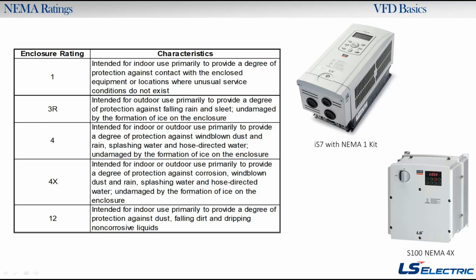Then there's NEMA 4 and NEMA 4X. Most people are usually requesting a NEMA 4X because a NEMA 4X can handle a hose being sprayed directly at it. We do have the S100 NEMA 4X, which is the second picture here. We offer that drive up to 30 horsepower, and it's commonly called a wash down drive. It has stainless steel screws on it and so on, so it's corrosion preventative. And the last one here is a NEMA 12. A NEMA 12 is another indoor rated package, but it prevents dust and dirt and some non-corrosive liquids. It's totally sealed, very similar to the 4X, but it's not waterproof.